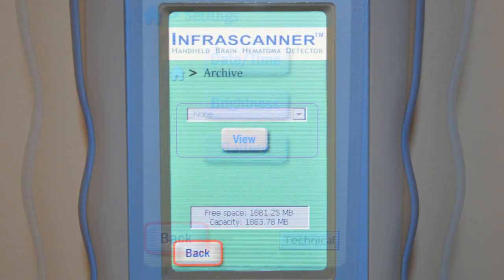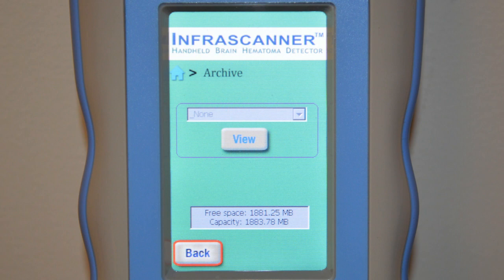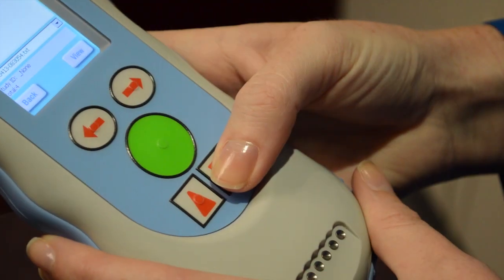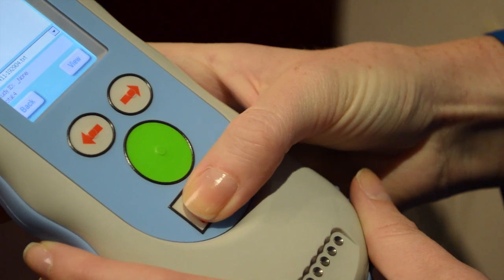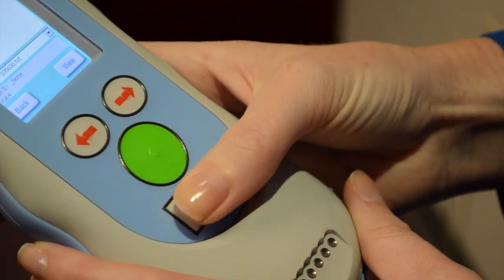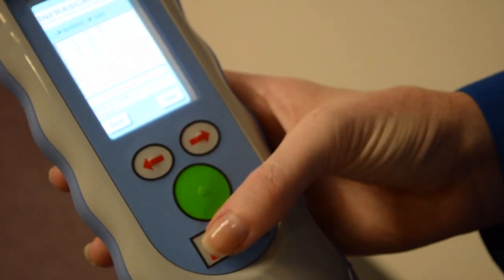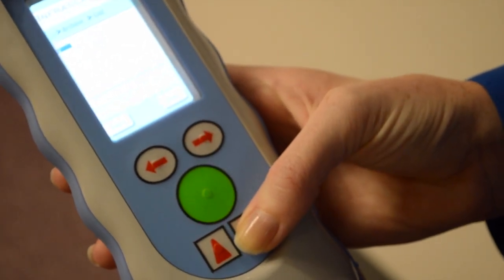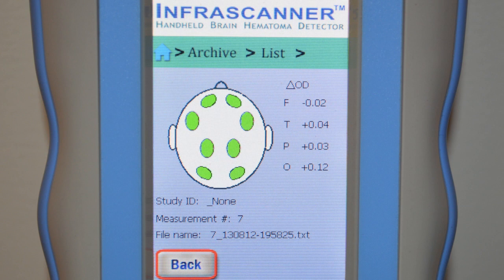The archive screen is where the measurements are stored. By selecting View and using the up-down arrow keys to select the scan to be reviewed, the scan measurement will be the number followed by the year, month, day, hour, minute, and second.